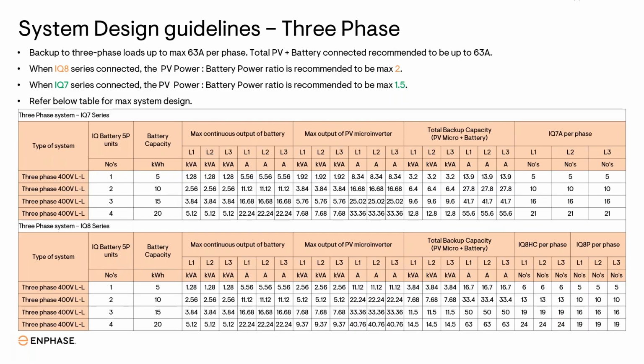and also for the installation. If you're going for a three phase, the formula will be the same here also. So per phase you are going to get 1.28, 1.28, 1.28 kilowatt of output. So 1.28 multiplied by 1.5 gives you 1.92. So the number of IQ7A inverters per phase will be 5, 5, 5, and for two batteries it will be 10, 10, 10. For three batteries it will be 16, 16, 16, and 21, 21, 21 for four batteries. Moving towards the 8 series inverters, 1.28 twice is 2.56. So for all three phases it will be the same. So IQ8HC per phase will be 6, 6, 6 for a single battery, and 8P will be 5, 5, 5. So these are the maximum inverters you can connect here.